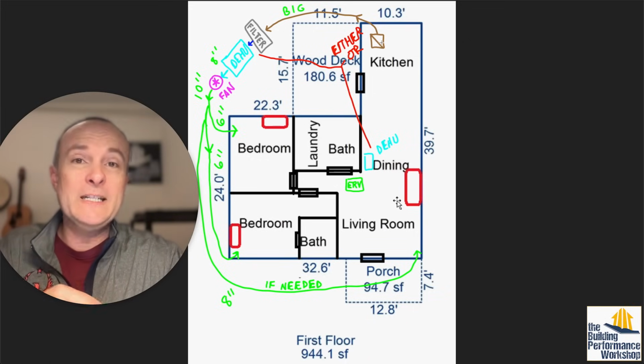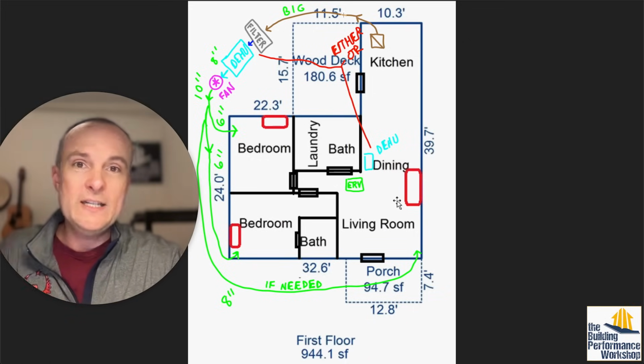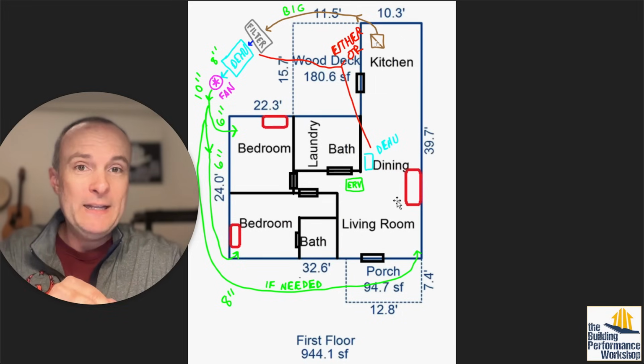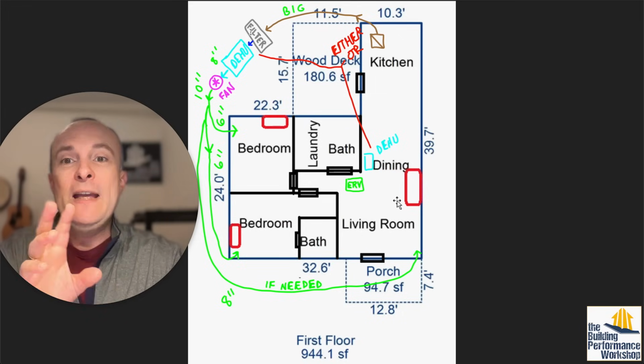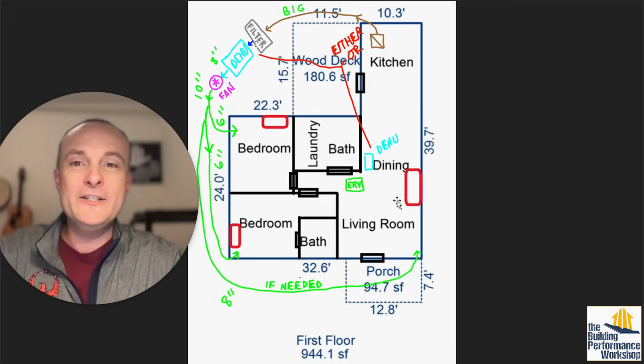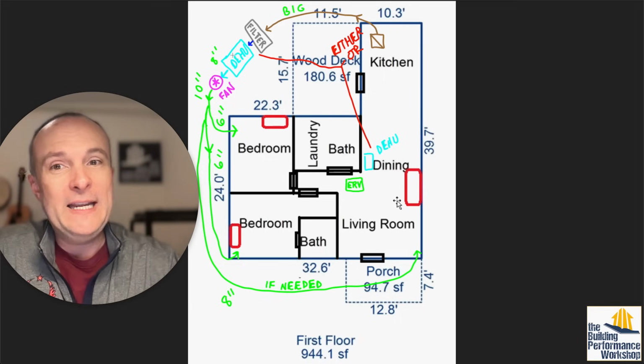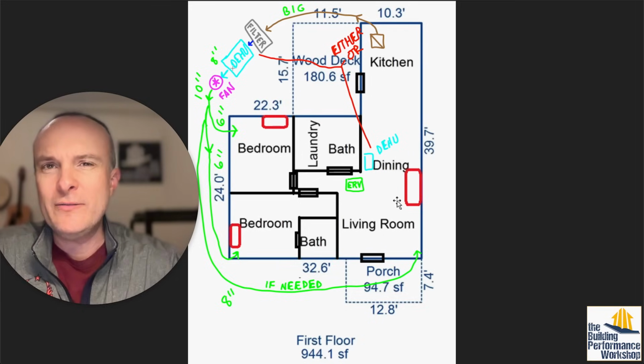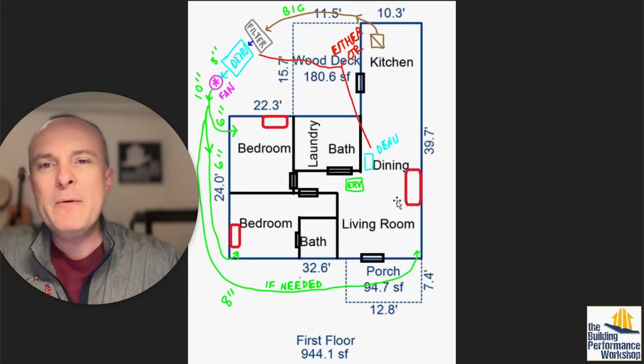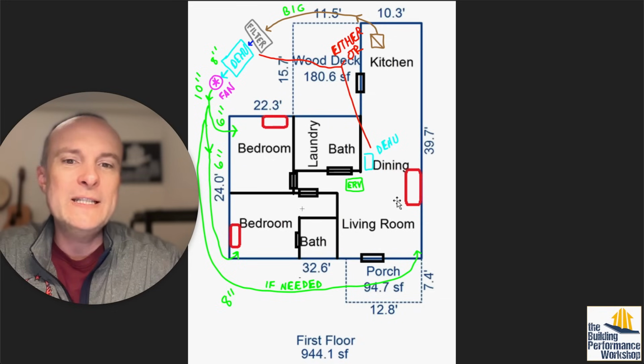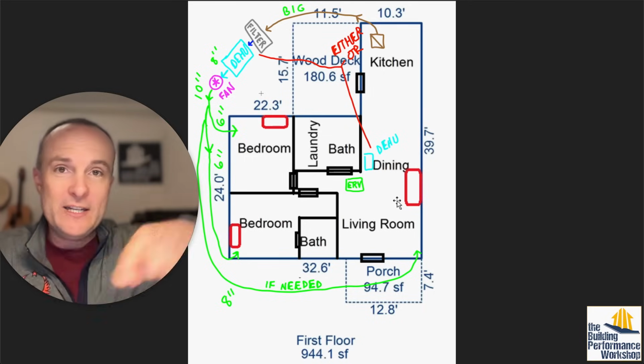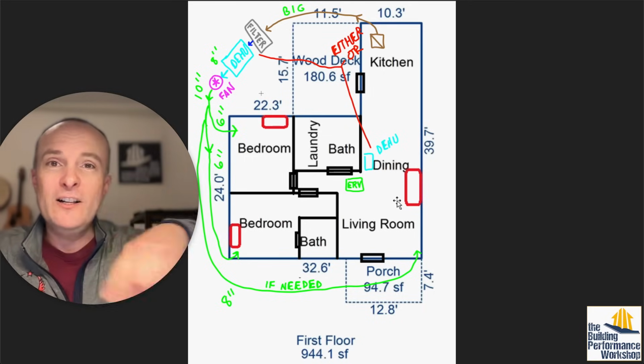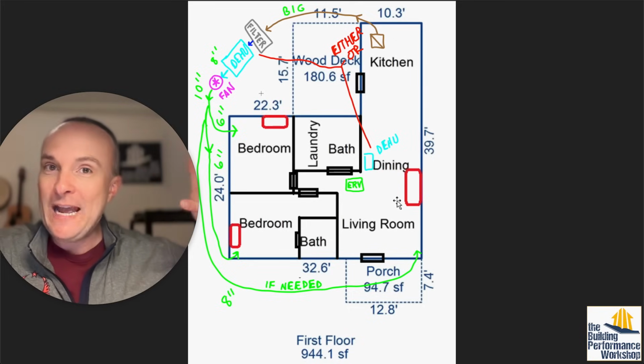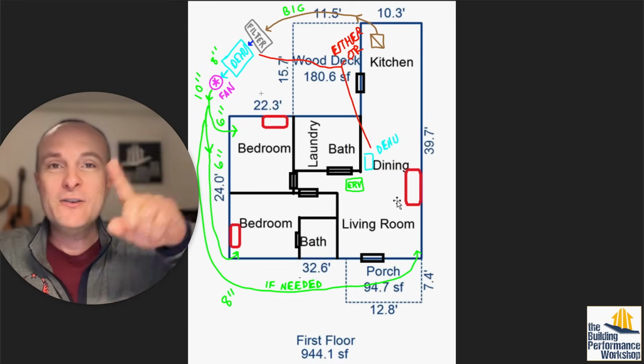This thing should be as big as possible, this return, because you just want it to be going slow. This would be loud if it's tighter. This will have a harder time if this is tighter also. Also, the dehumidifier being in line here introduces a special issue that I'll get into later. But basically, this is going to then induce this cycle of air past the ERV and the dehumidifier and back into the kitchen, and then we just basically have this loop like a little lazy river at a water park, right? So it's just constantly going around and around.